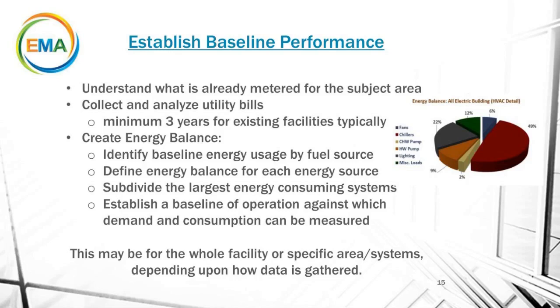Okay, the next one: to determine the breakdown of energy consumption, do you perform actual measurements at each piece of equipment, or have energy modeling done? It depends—how much money do we have, how much time do we have. I like doing it at the equipment and system level, so I'm capturing actual equipment full load amps and usage during commissioning and bringing that online. But from a system perspective, I like verifying system performance against the sequence of operations. Hopefully that answers your question.